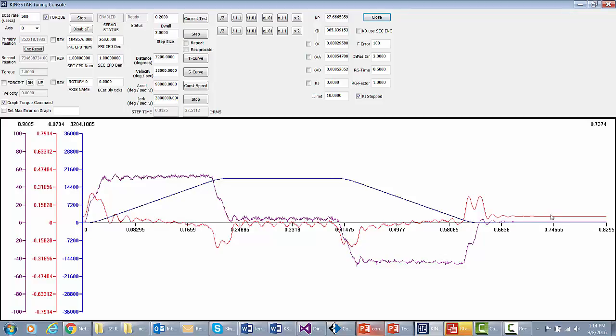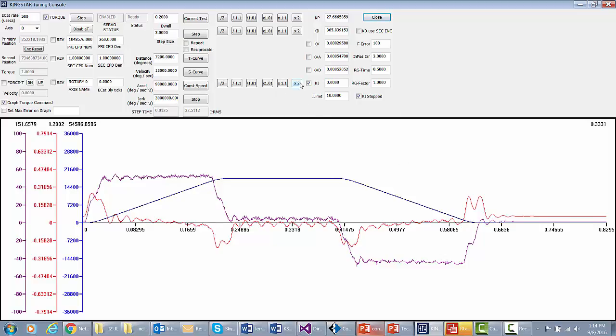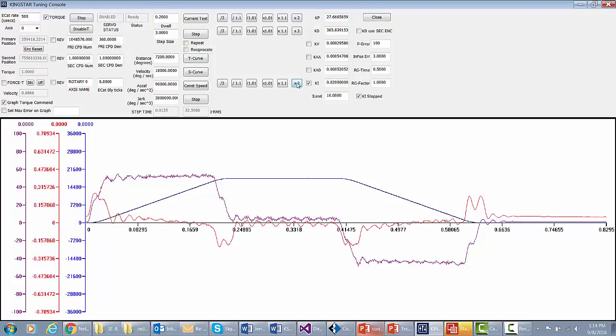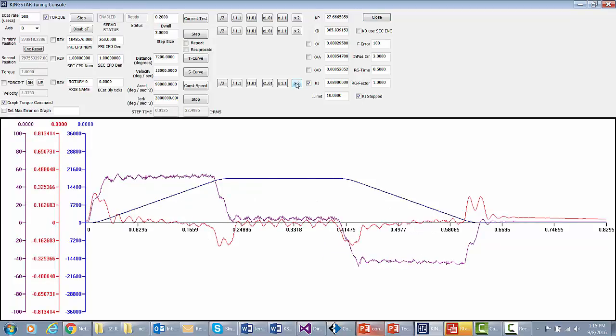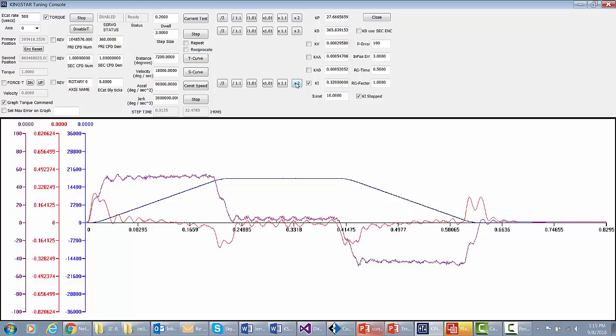We're going to use KI to try and get rid of that. At this point, the derivative term is no good because we're not moving. None of the KVs or KAs are working because, again, we're not moving. So KP is simply not enough to overcome the friction in that seal. So we're going to use the integral where we're going to let that error build tick after tick until finally it becomes enough to cause motion, and you can see it working its way down even as we speak.